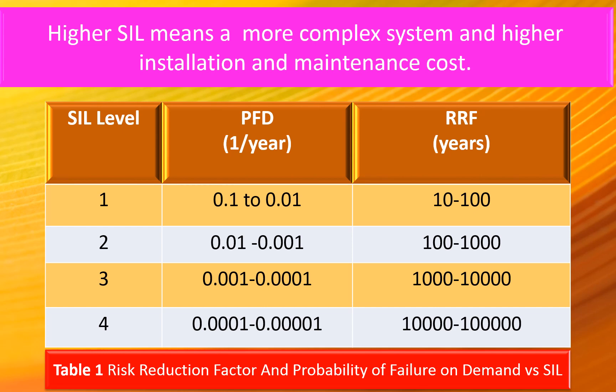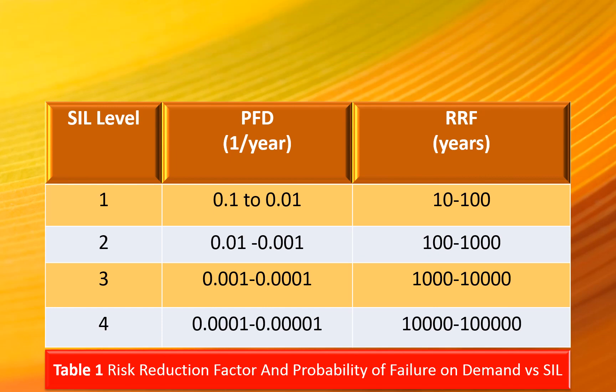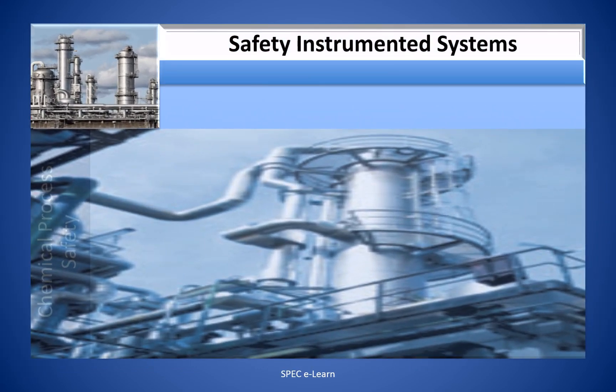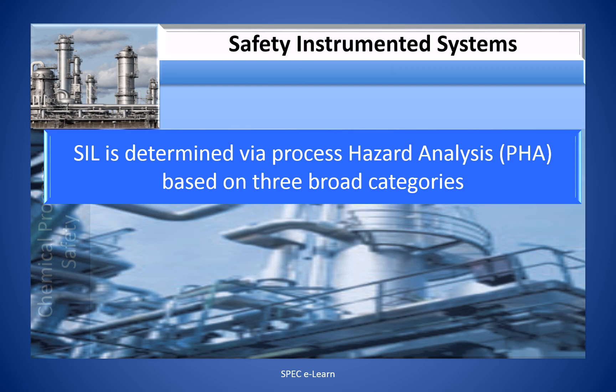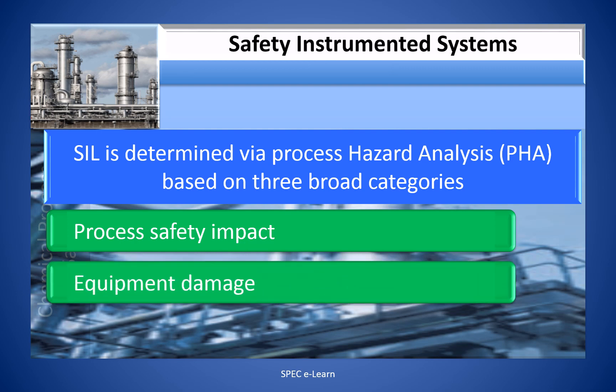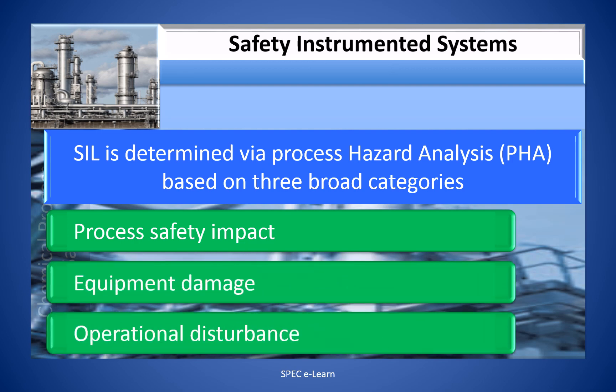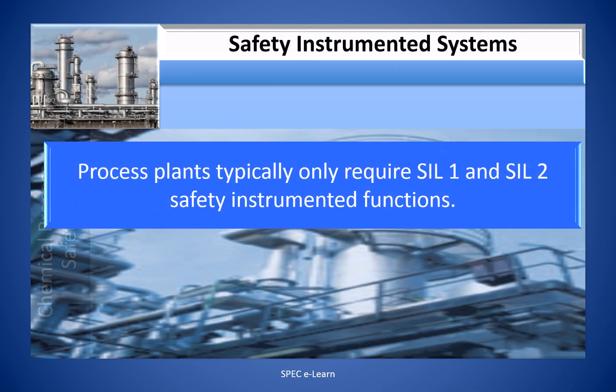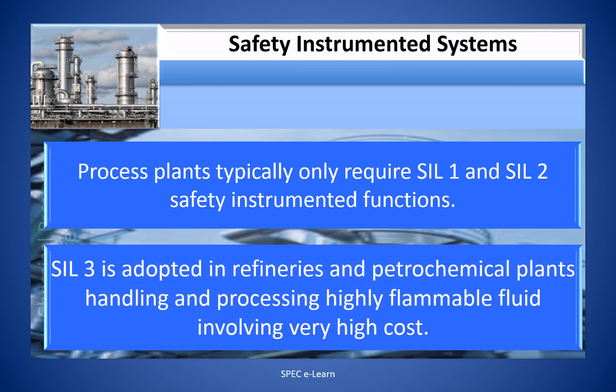Higher SIL means a more complex system and a higher installation and maintenance cost. SIL is determined via process hazard analysis based on three broad categories: process safety impact, equipment damage, and operational disturbance. Process plants typically only require SIL 1 and SIL 2 safety instrumented functions. SIL 3 is adopted in refineries and petrochemical plants handling and processing highly flammable liquids, involving very high cost.